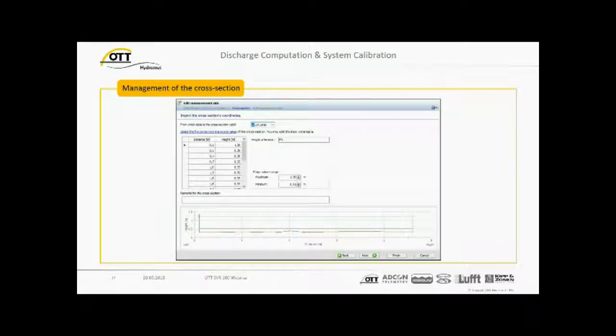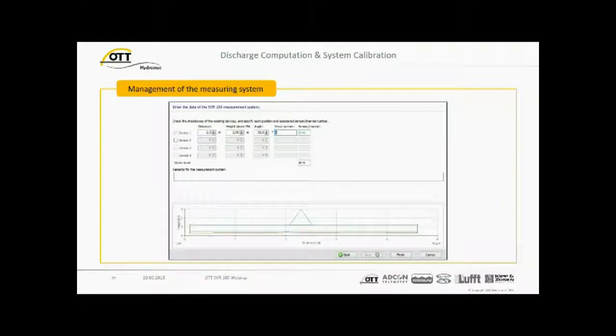Then you assign a date from when it's valid. You enter the height reference. Is it meter above datum, or meter above the bottom of the channel, whatever. And you need to define the values from minimum to maximum, so the range for which you want to have calibration factors computed finally.